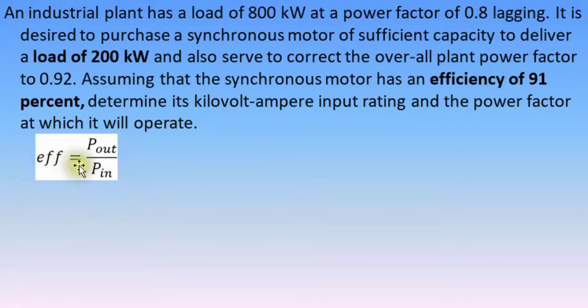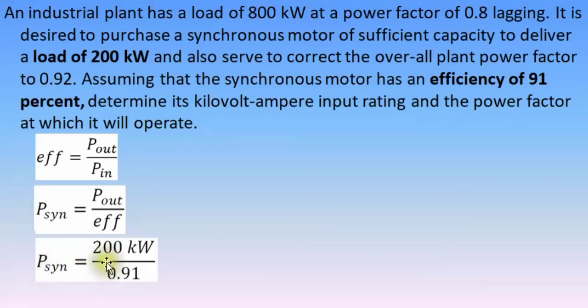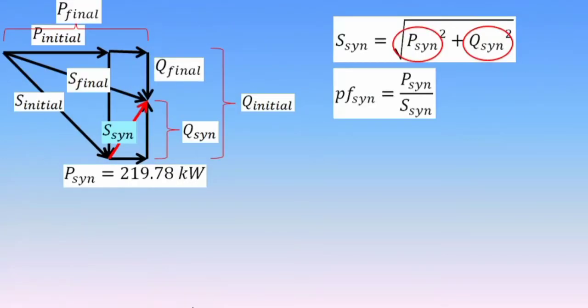Cross-multiply the efficiency and the power input we have. Power input equals power output divided by the efficiency. And let's say that this is the synchronous motor power input. Substitute the values. We have 200 kilowatts divided by 0.91. The value is 219.78 kilowatts. Now that we have the value of its effective power input, let's also determine its reactive power input.